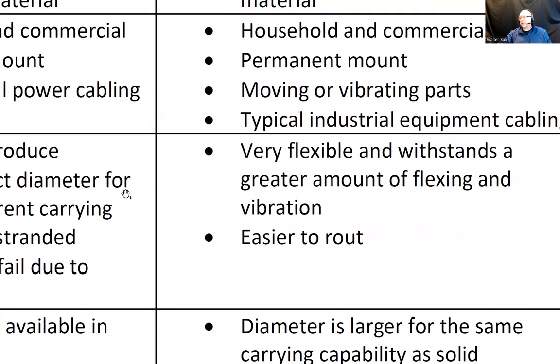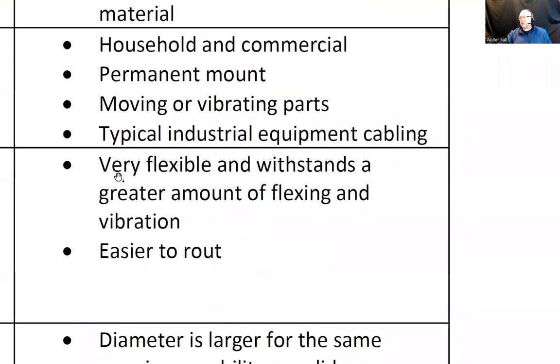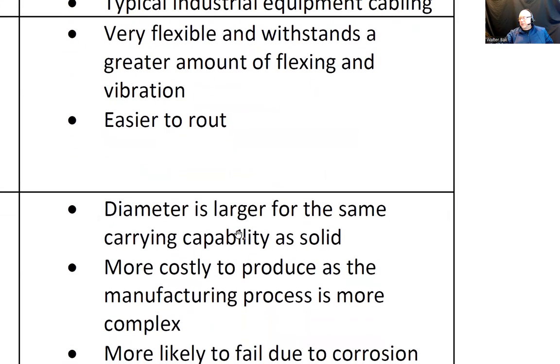Advantages: very flexible, withstands a greater amount of flexing and vibration, and it's easier to route when pulling the wire through pipes or conduits or around corners, because it's stranded, not solid. Disadvantages: the diameter is larger for the same current carrying capability as solid.